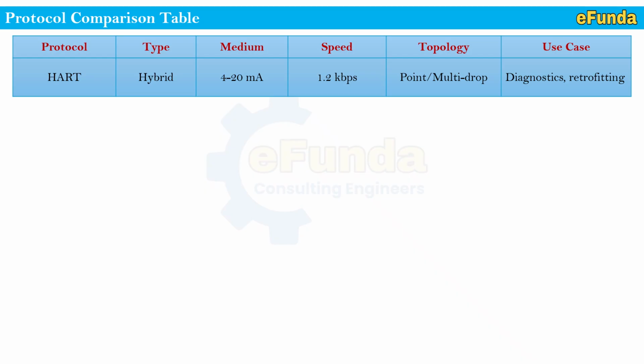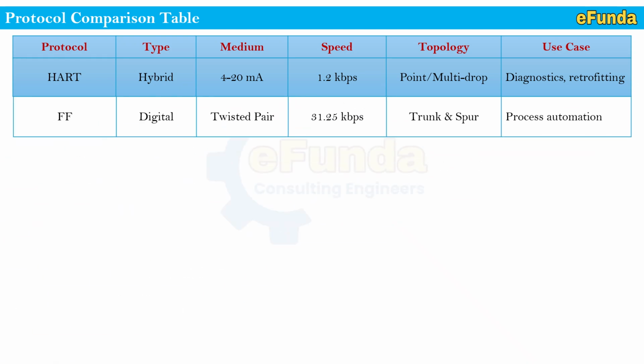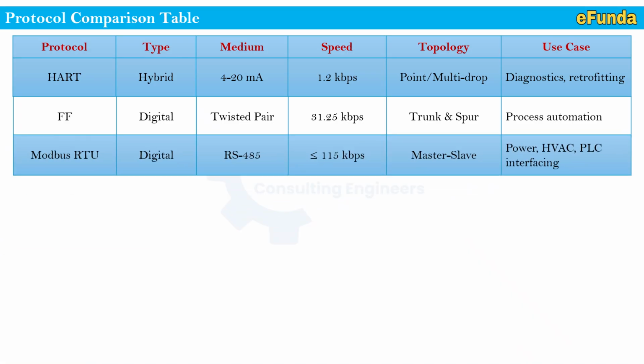Now we have reached the point of understanding the protocols. For simplicity, we will see the protocol comparison table. Here we will see the protocol type, medium, speed, topology and uses for easy understanding. First, HART is a hybrid type, medium 4 to 20 milliamps, speed 1.2 kilobits per second, topology point to point or multi-drop, used for diagnostics and retrofitting. FF, that is Foundation Fieldbus, is digital type, twisted pair as a medium, 31.25 kilobits per second, trunk and spur type configuration, used for process automation. Modbus RTU, digital type, RS485 as a medium, speed less than or equal to 115 kilobits per second, master slave configuration, used for power, HVAC, PLC interfacing, etc.